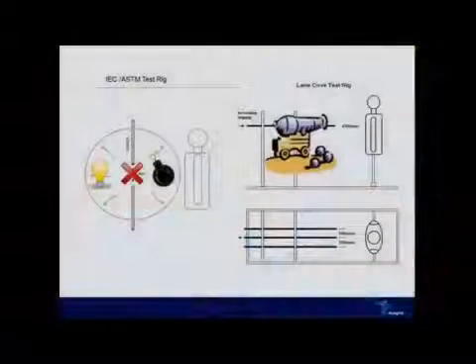So to better represent reality, we should use a copper electrode test rig. So that's what we did. We took Dr. Sweeting's advice. Now, my paraphrase of Dr. Sweeting's research is he's shown that a fault on parallel electrodes becomes a motor-driven plasma cannon, firing superheated ionised gas in a direction, and far less of a light bomb where radiant energy is dissipated evenly in all directions.